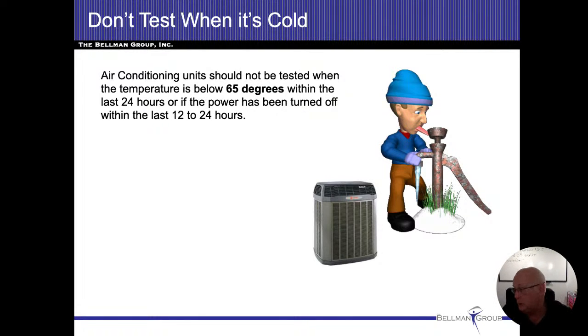Testing air conditioners. This is a big one. All right. Most home inspectors will use the temperature is 65 degrees. And I'll be honest with you, a lot of air conditioning systems can go all the way down to 50 degrees, and they'll run just fine.